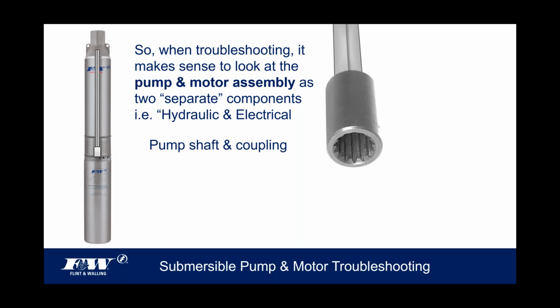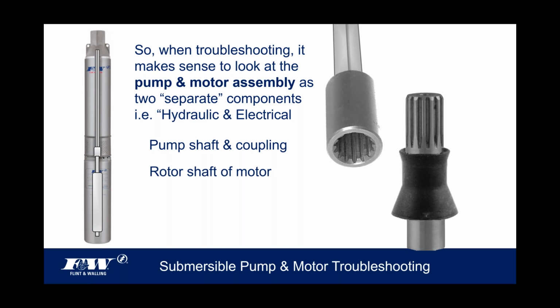If we look at the pump end, the pump is going to have a hex shaft with a coupling on the end of it. This is fairly generic. If you break a submersible pump and motor apart, you're going to see exactly what I'm talking about here. There is a hex stainless steel shaft with a pressed coupling. You can see it is splined. And that mates with the shaft that comes off the motor, better said, the rotor, as you can see on the right-hand side of your screen.